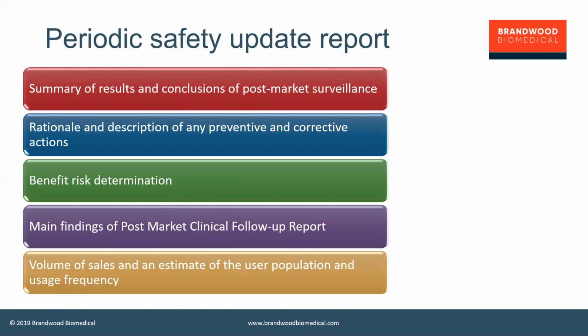And then the periodic safety update. This is something that gets done from time to time, where you summarize your post-market surveillance, and you provide a rationale if you've had to take any corrective actions in response to things you've learned in the post-market surveillance, look at risk again, provide the main findings, and put it in the context of the number of devices supplied. So there's a denominator as well as a numerator. How many things went wrong, or what did you observe in the post-market, and what was that as a proportion of the number of devices sold? So we're looking at rates of occurrence.